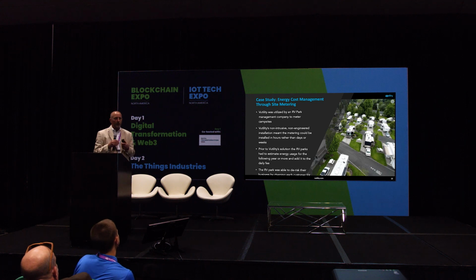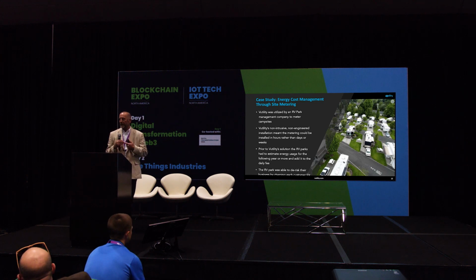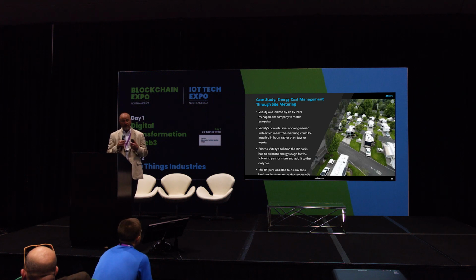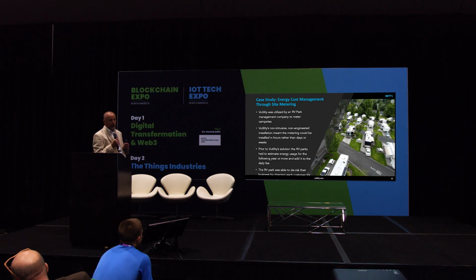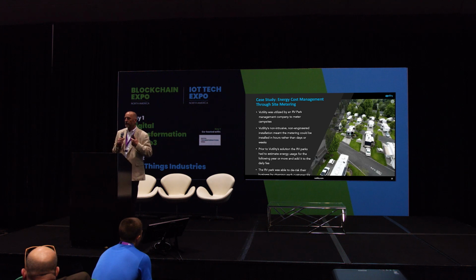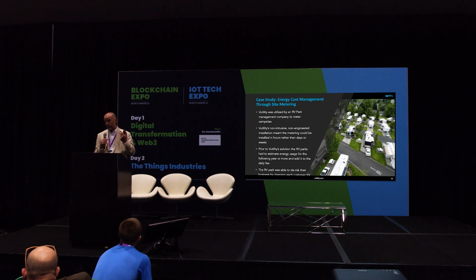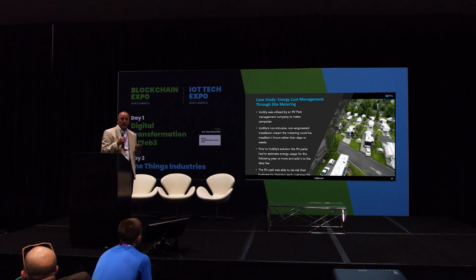They were looking for a way to quickly start monitoring every campsite. So they went in and put hot drops in at each campsite. Each campsite had two 220 volt two-phase breakers and one 110 volt breaker, and now they're able to meter this.